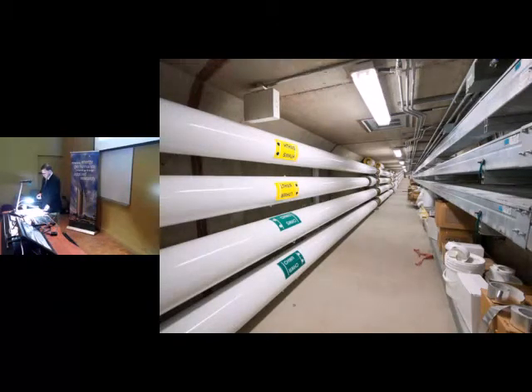The terminal building is heated using hot water generated at the central utilities plant, and we use a unique cascade approach to make use of that hot water as effectively as possible. We send hot water at a relatively high temperature, 180 degrees Fahrenheit, which is 82 degrees Celsius, into the building.